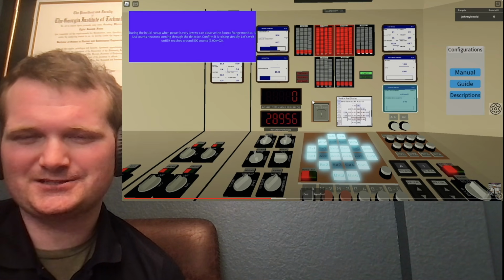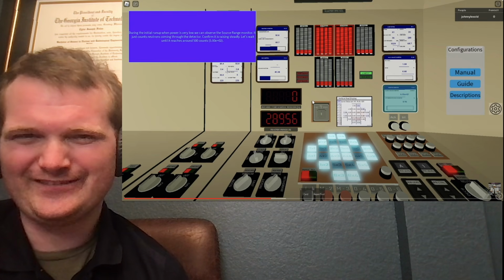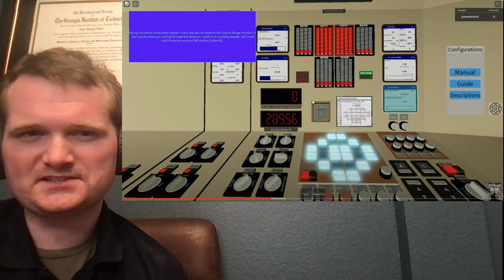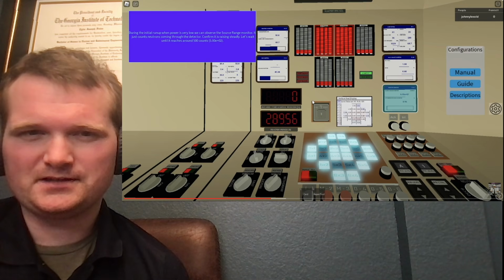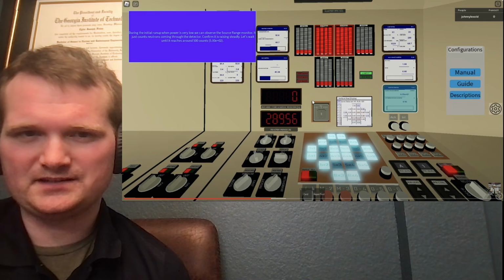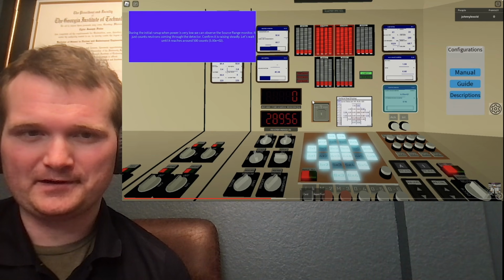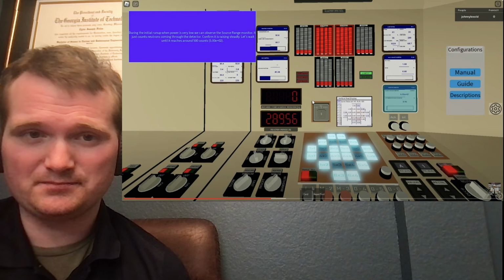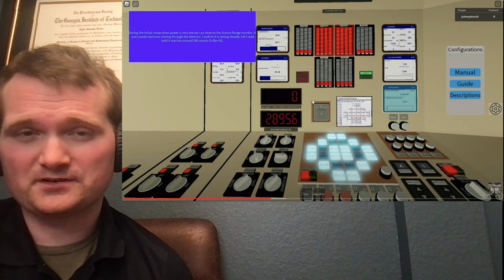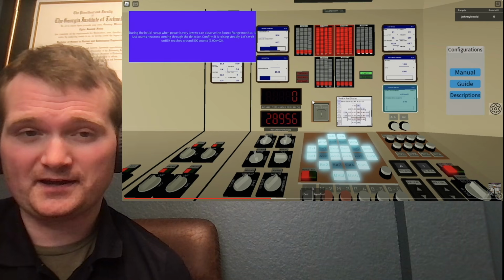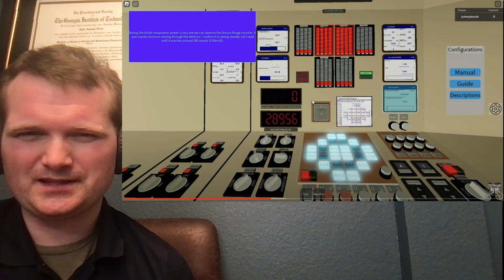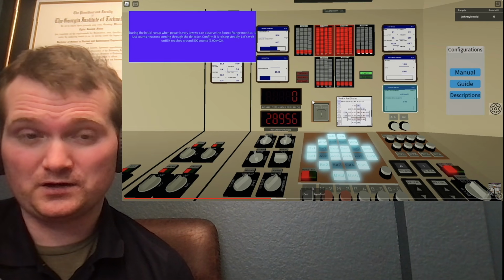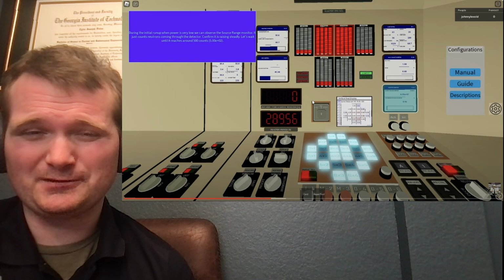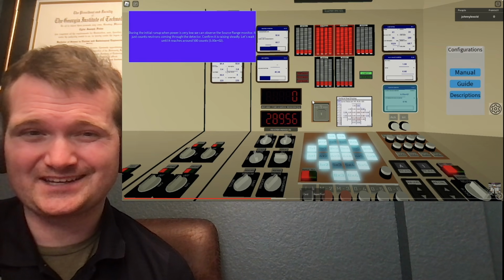The plant I worked at did not use this thing. I've never been a fan of reactor period. Instead, we use something called startup rate. The startup rate is decades per minute, a decade being a factor of 10. So if your startup rate is 1, power is going to go up by a factor of 10 in a minute. If it is 3, power is going to go up by a factor of 1,000 in a minute. And the startup rate limit at the plant that I worked at was 1. We would often start up at around 0.3 to 0.5 decades per minute.